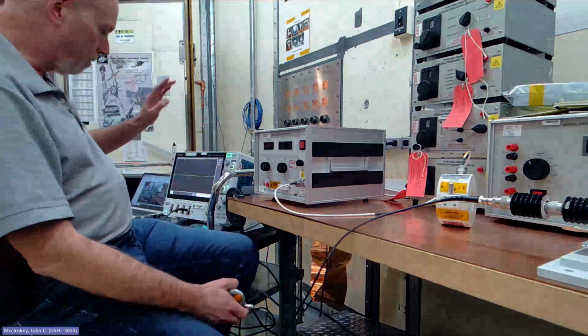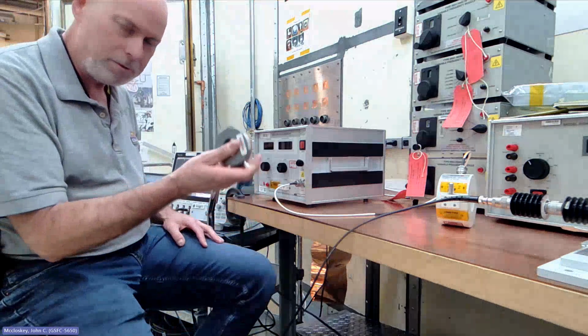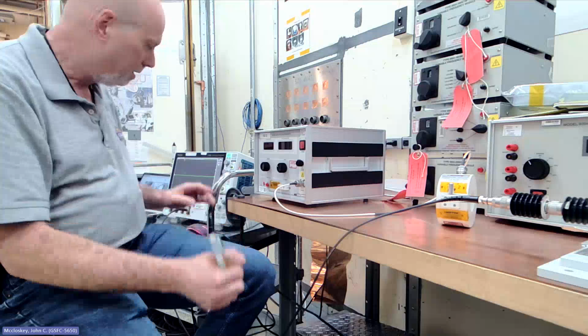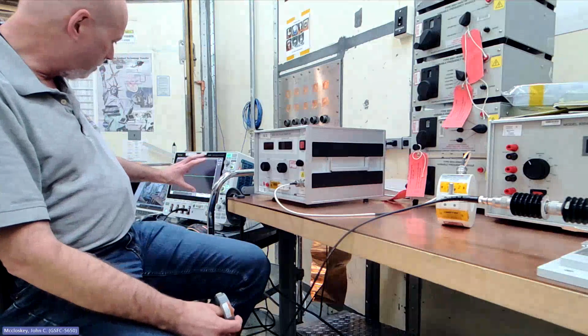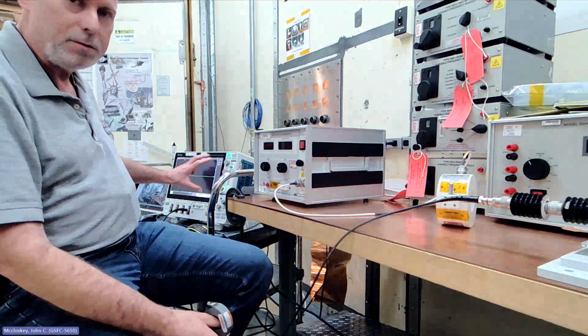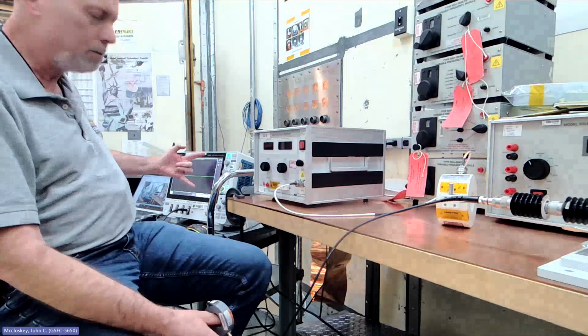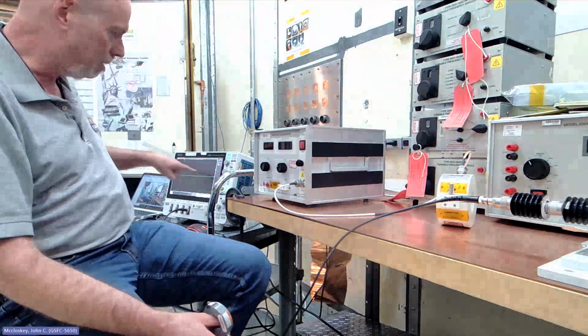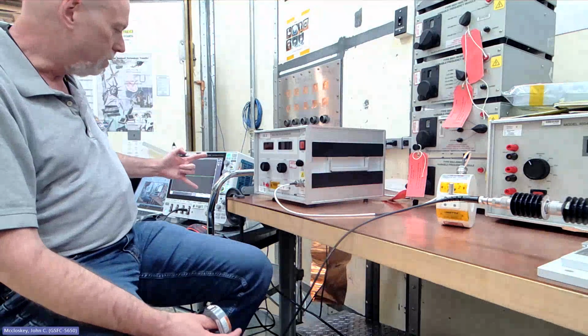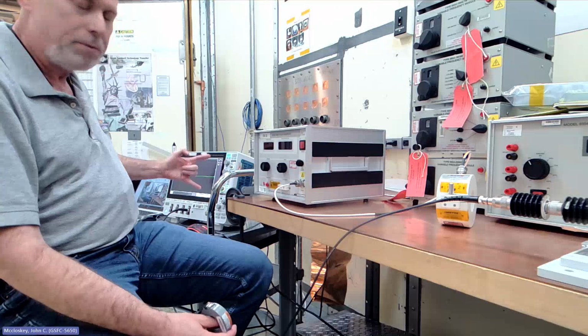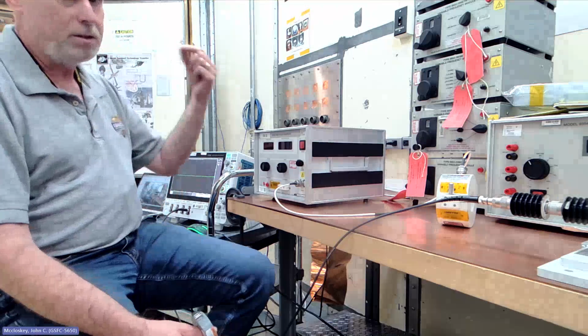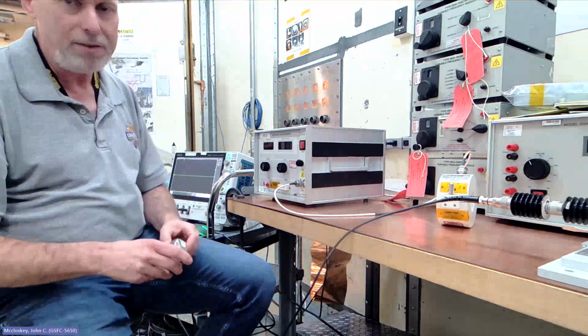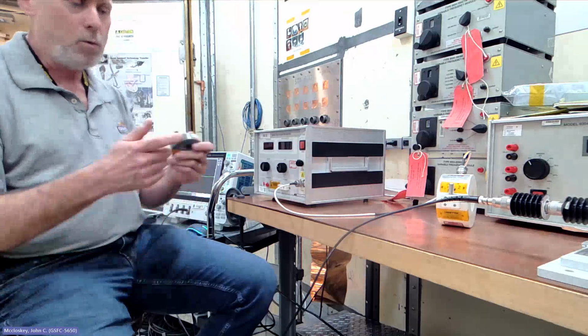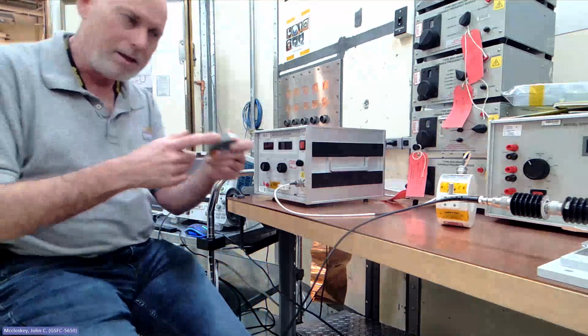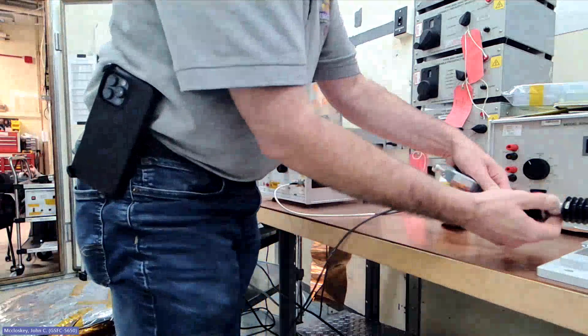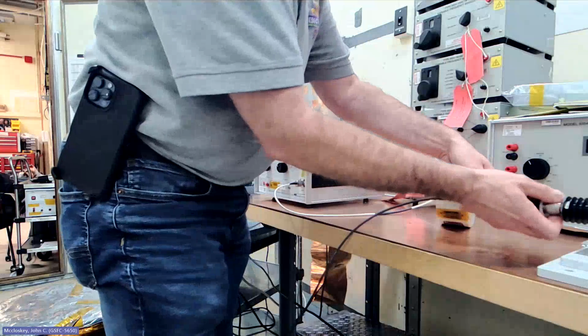So 30 amps into this current probe is going to produce 30 volts at the output. And I'm limited to a range of plus and minus 5 volts on the scope, or a total span of 10 volts. I'm going to keep the 0 line in the center. So I'm limited to a span of plus minus 5 volts, and if I could see as much as 30, that's a bit high. So I'm going to want to put some attenuation at the output of my current probe. So 20 dB should do it.